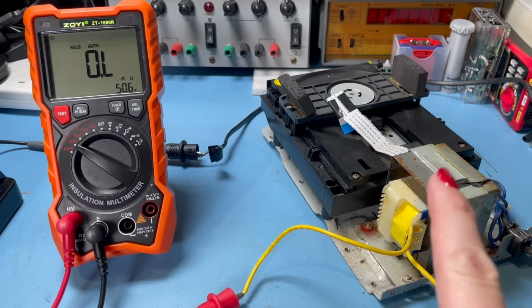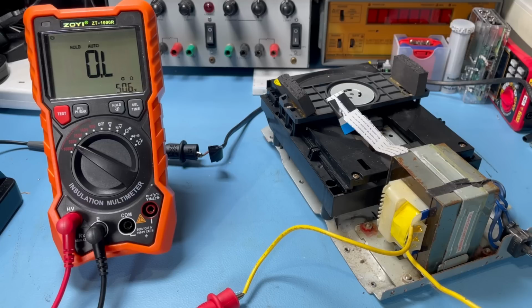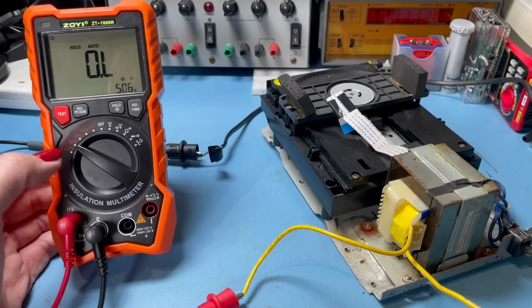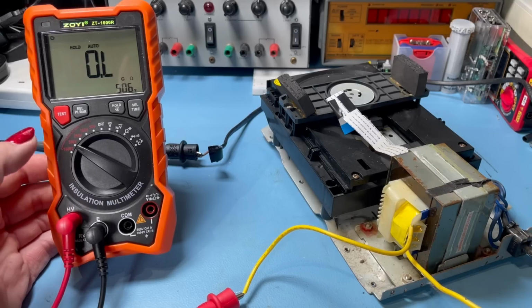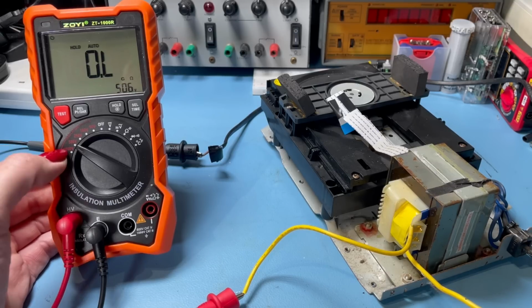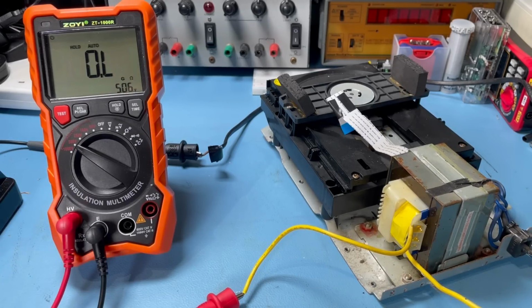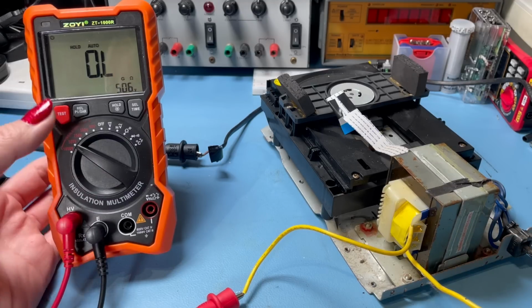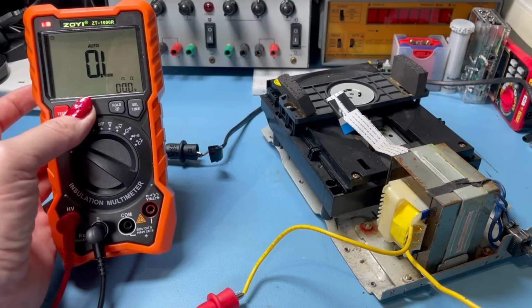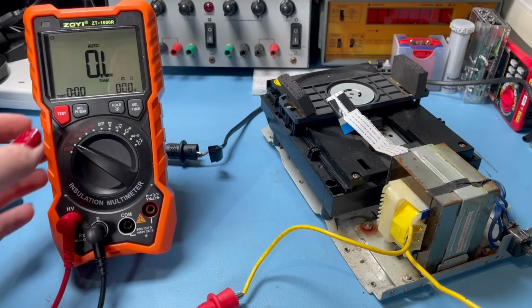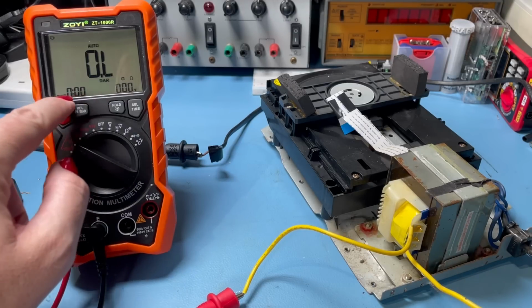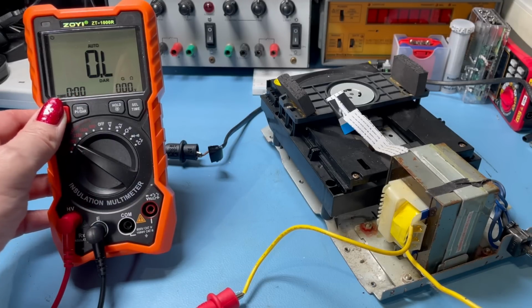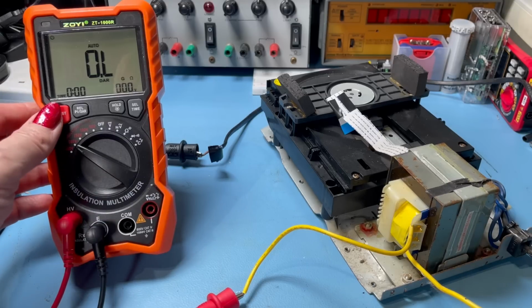Now, another test we can do here while we're hooked up to our transformer is a DAR, or dielectric absorption ratio test. Now, this will compare the insulation resistance values at 15 seconds and 1 minute. So we're going to go ahead and do that now. I'm going to stay at 500 volts and I'll speed up the footage so you can see what the results of the DAR test is. So we're going to go into DAR mode. There we go, you can see DAR there. It will automatically time it for you there. So just press test and your red warning triangle will come on. Keep your hands away.